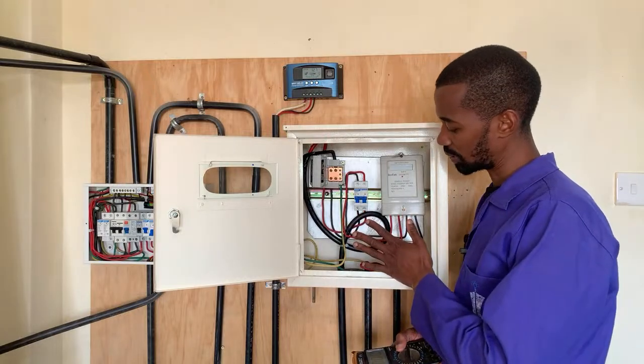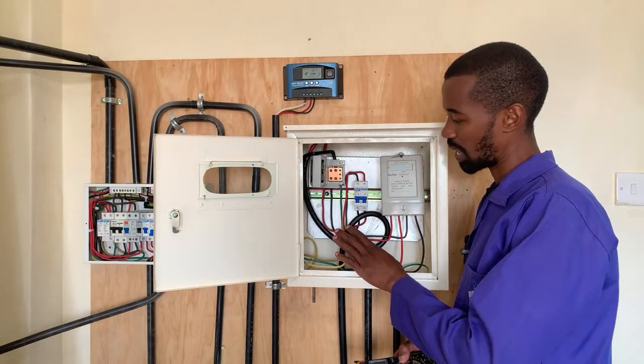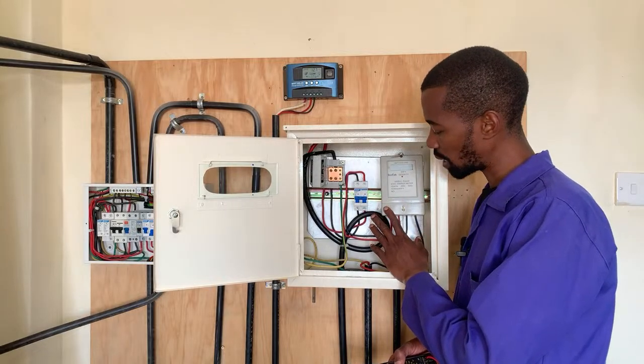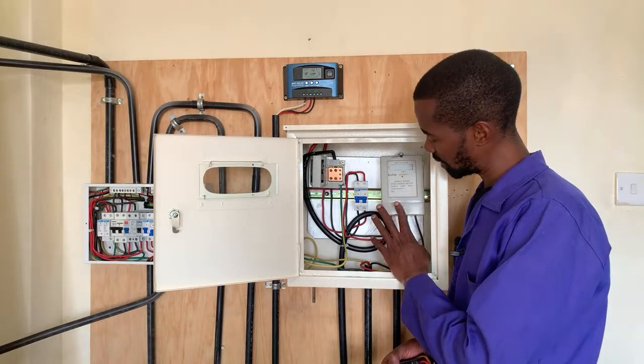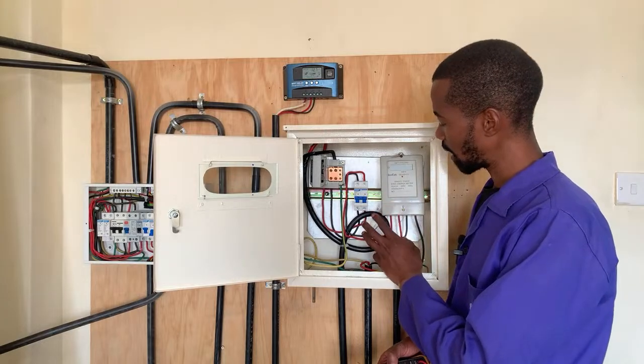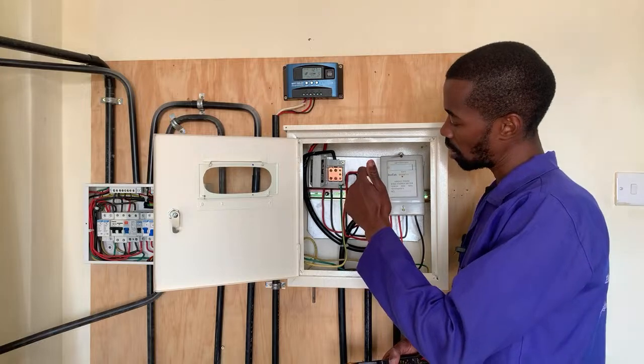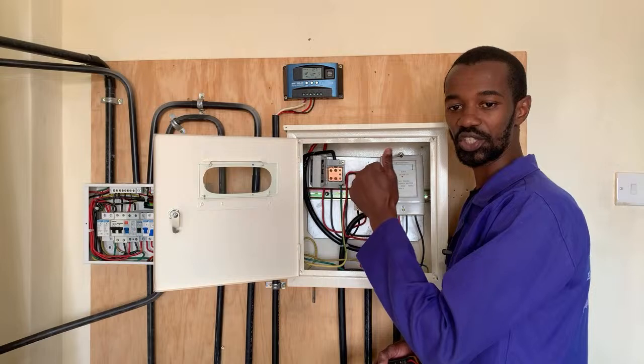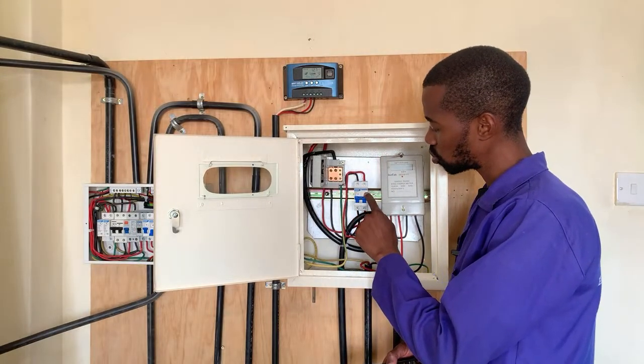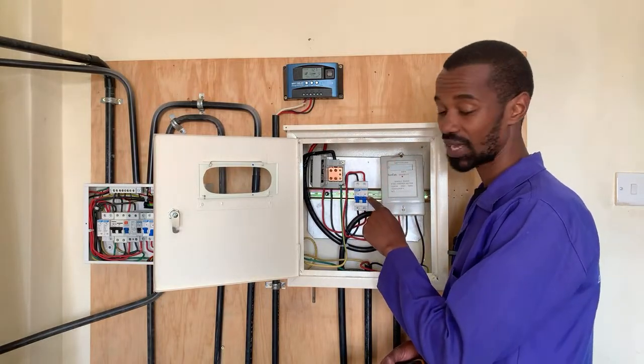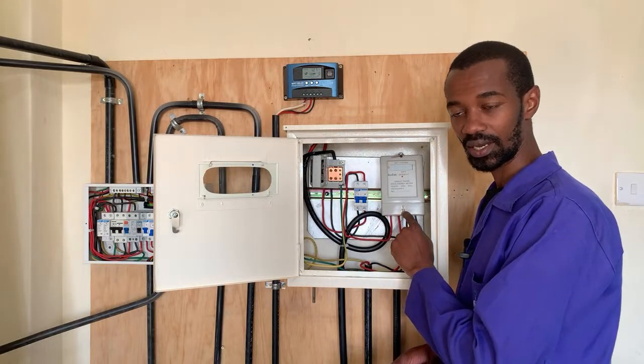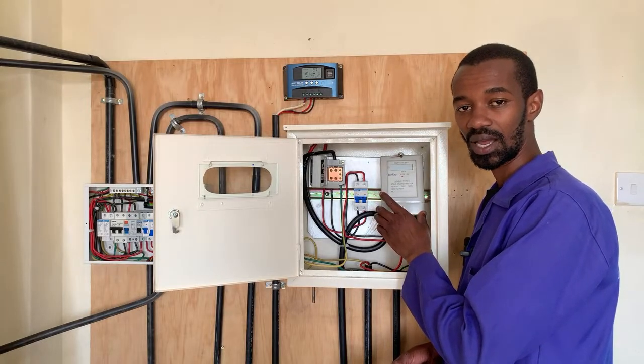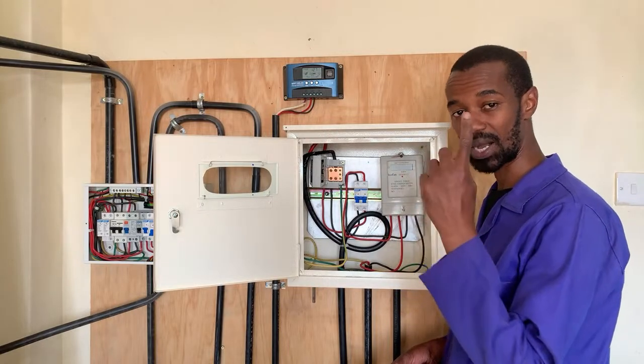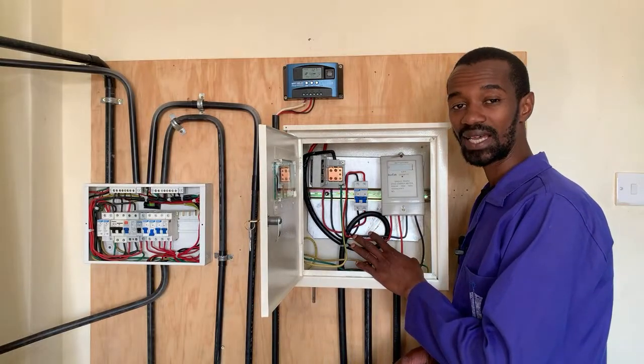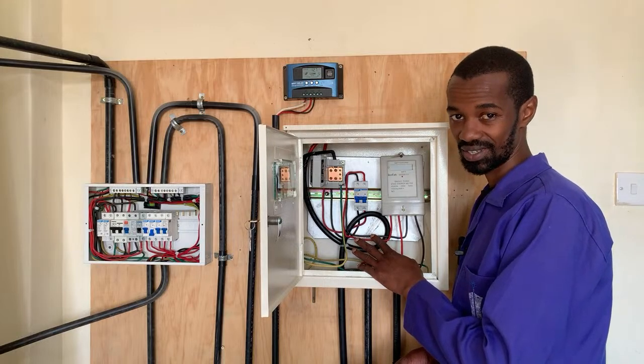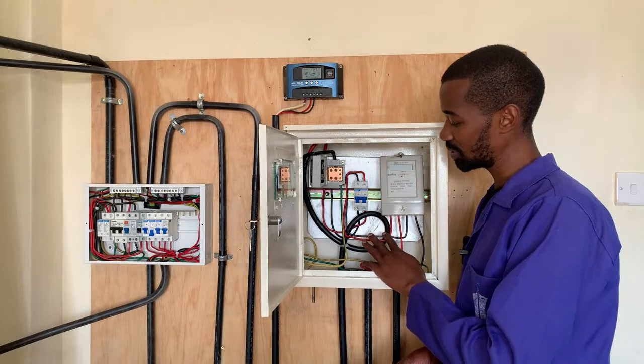So we will start at this meter box. The customer has said they don't have power. I have walked you through the possibilities of trouble in this meter box. Let's assume everything is okay here: we have input from the pole, check. Output from the double cutout, check. Output going to the double pole or main switch, check. Output from the main switch to the meter, check. Output from the energy meter exiting to our consumer unit, check. But there is an issue, the power does not reach the consumer unit. So it means we are not yet done with this meter box. So what do we do?